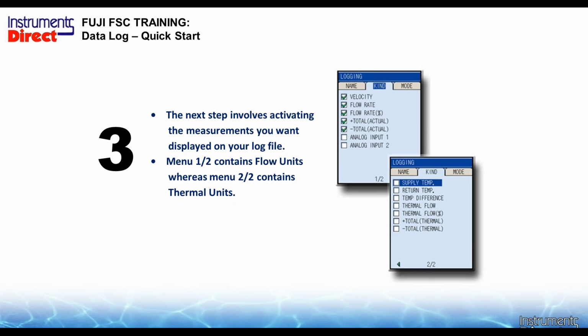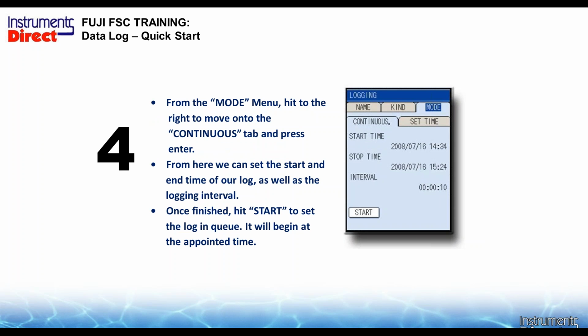The next step involves activating the measurements that you want. Again, if you had some of the older meters that only stored 100,000 data points, the data you stored was critical because you only had 100,000 data points. Now you have a gazillion data points, so that's not a problem. So it depends, again, what you're going to do with the data. You can log velocity, flow rate, total, temperature. You can get into the energy side where you can record BTU, supply and return temperature and flow, and all those different things just by checking off a specific box. So select what you need, and she will log away.